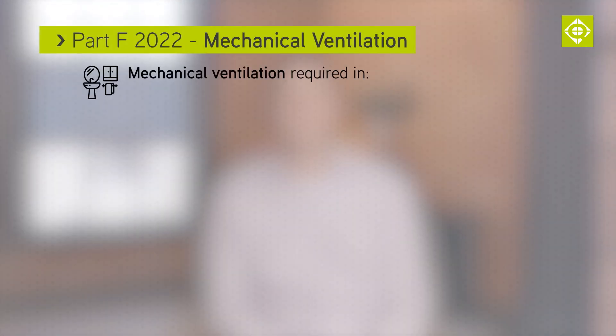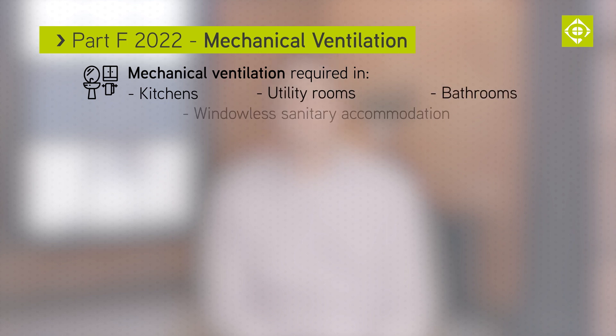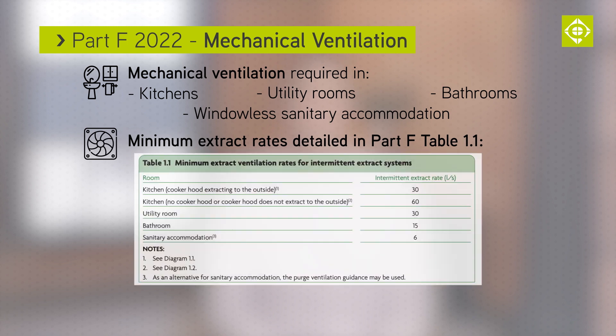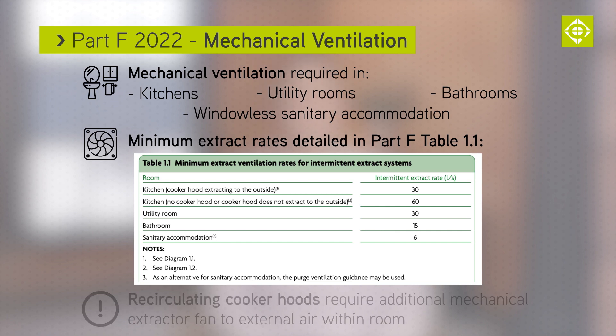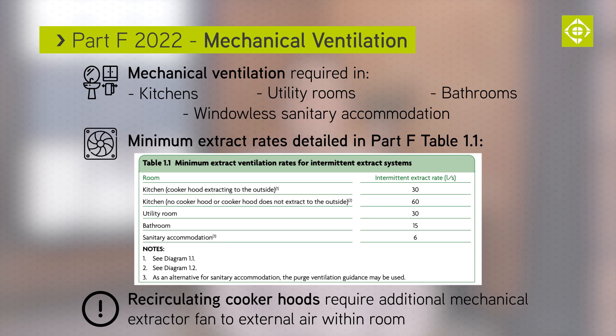Mechanical ventilation will be required in kitchens, utility rooms, bathrooms and windowless sanitary accommodation. Minimum extract rates are detailed in Table 1.1 of the new approved document. There is now clear guidance that recirculating cooker hoods require an additional mechanical extract fan to external air within the room.